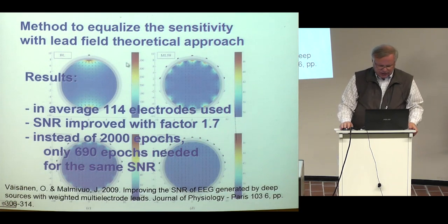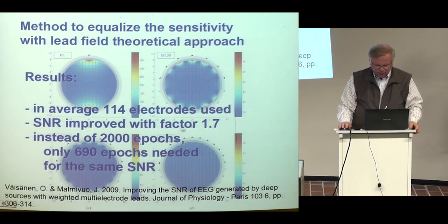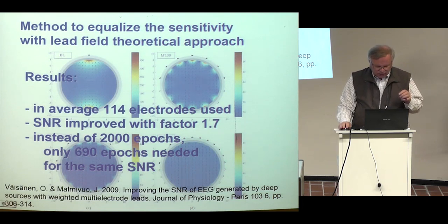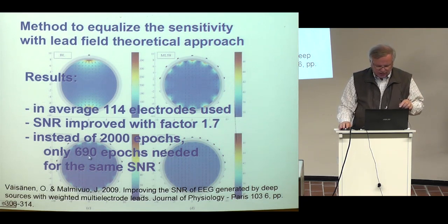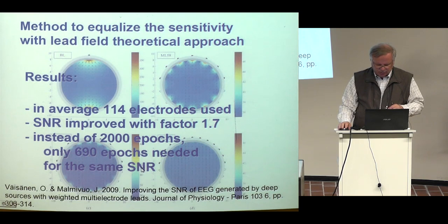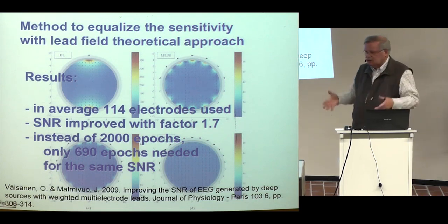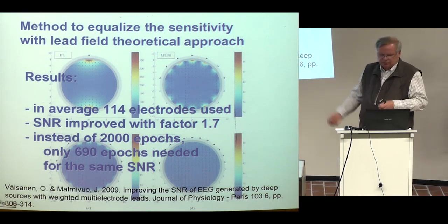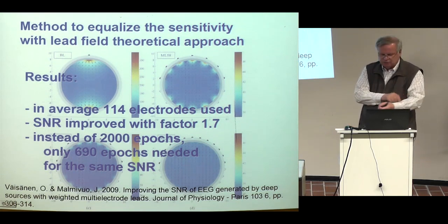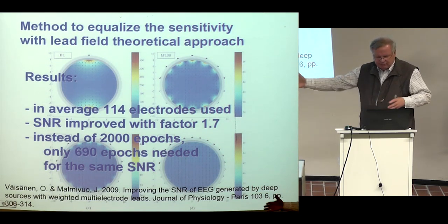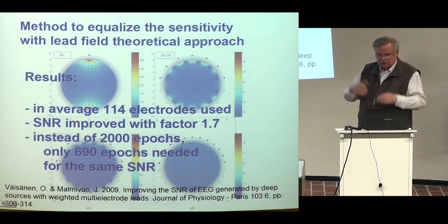We calculated the results: on average with 114 electrodes used, the signal-to-noise ratio improved by a factor of 1.7 — not very much. But instead of 2000 stimulation epochs, only 690 epochs are needed for the same signal-to-noise ratio. This is a remarkable, important improvement when thinking about how unpleasant it is for the patient to sit for all 2000 epochs. That can be reduced to 690 epochs to get the same signal quality.